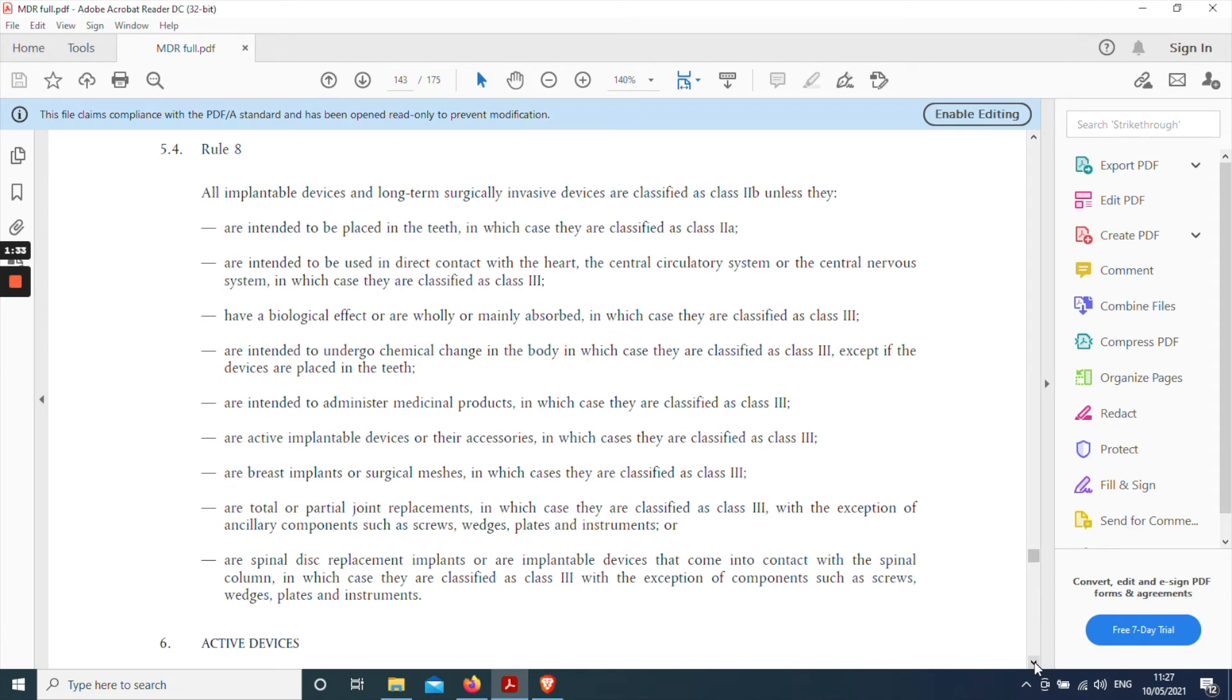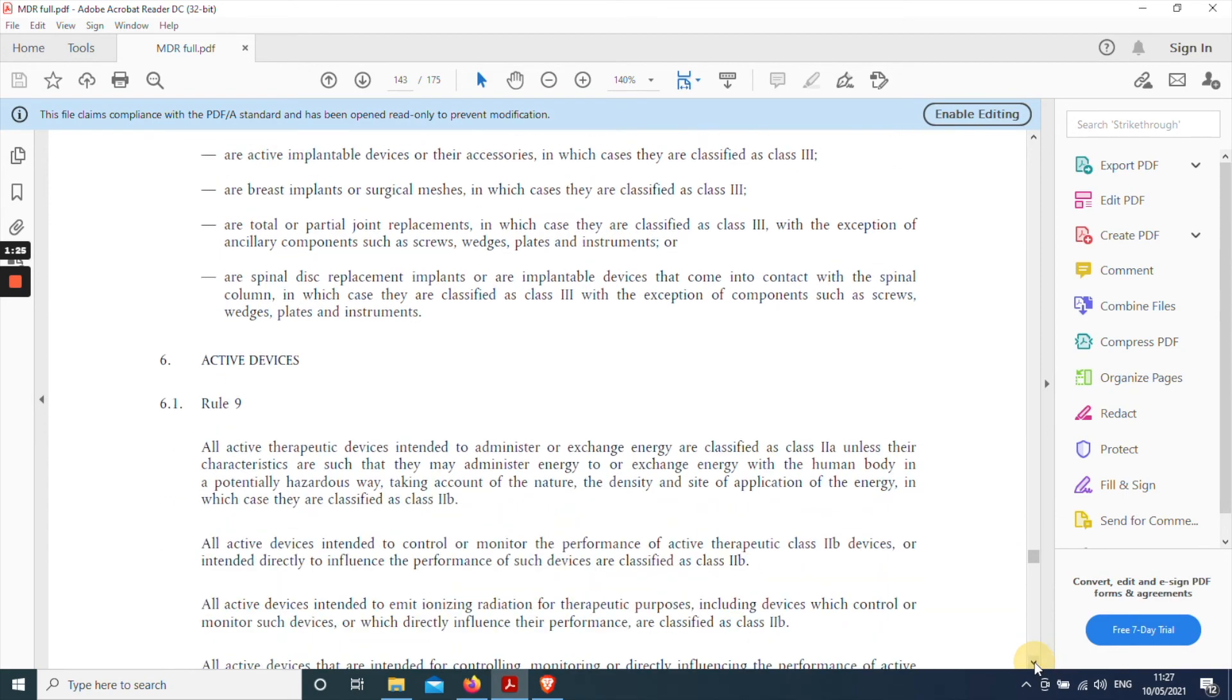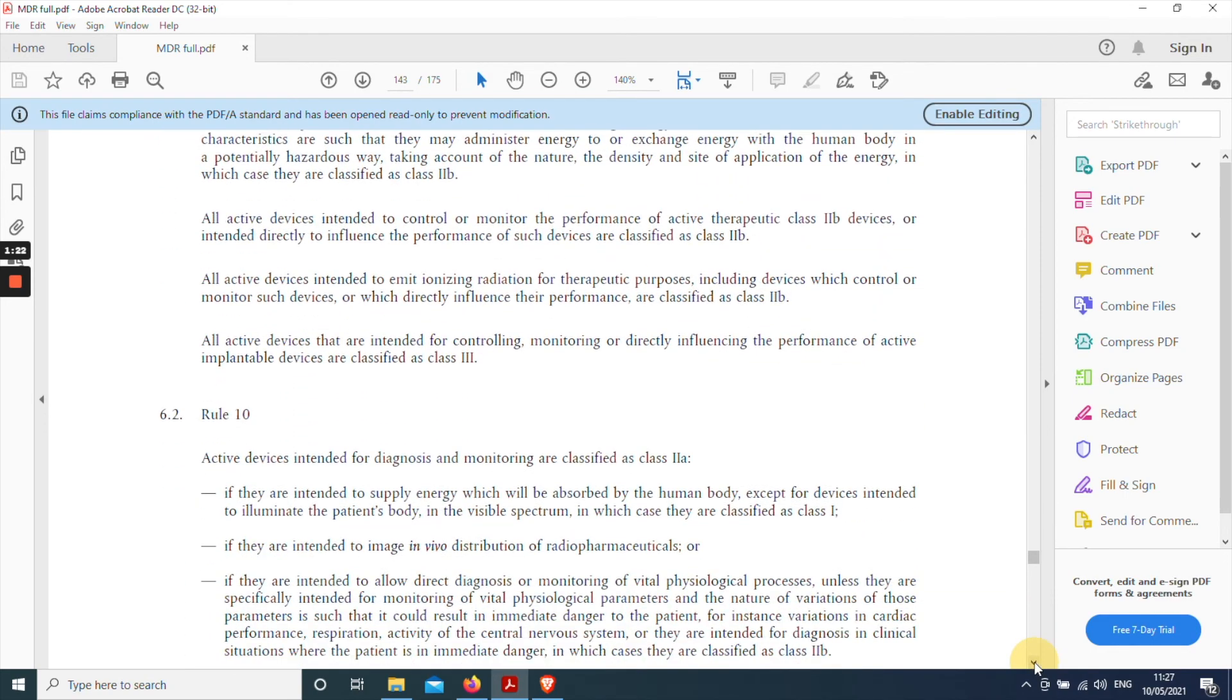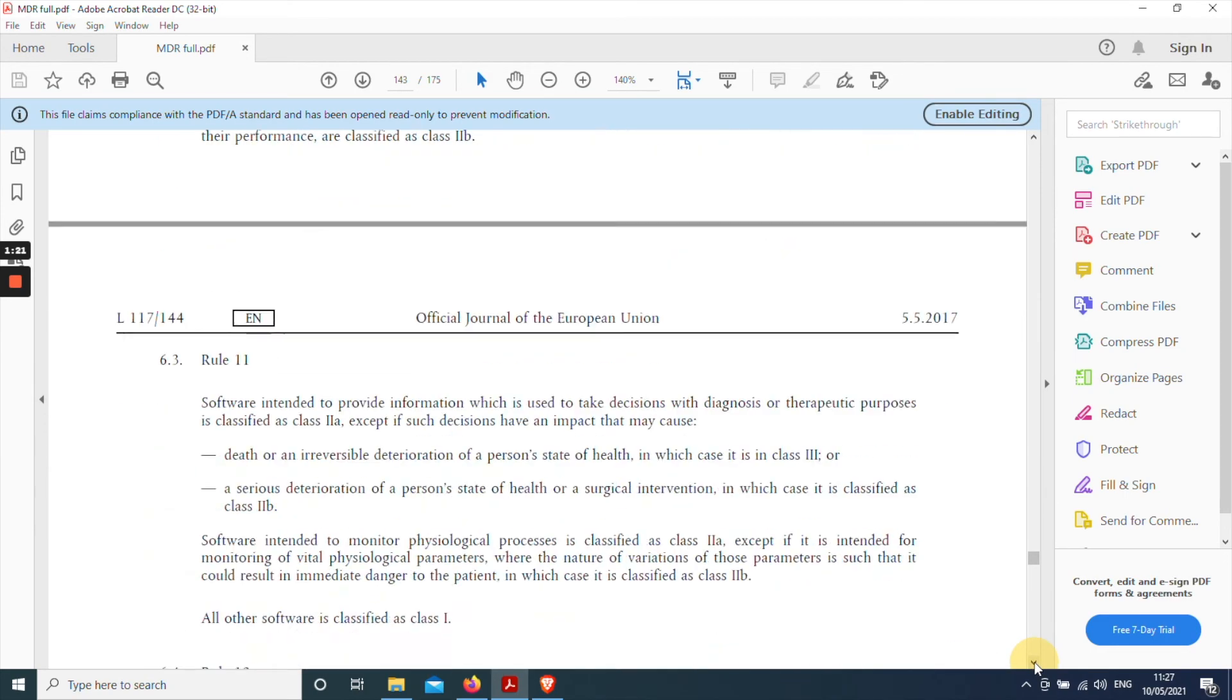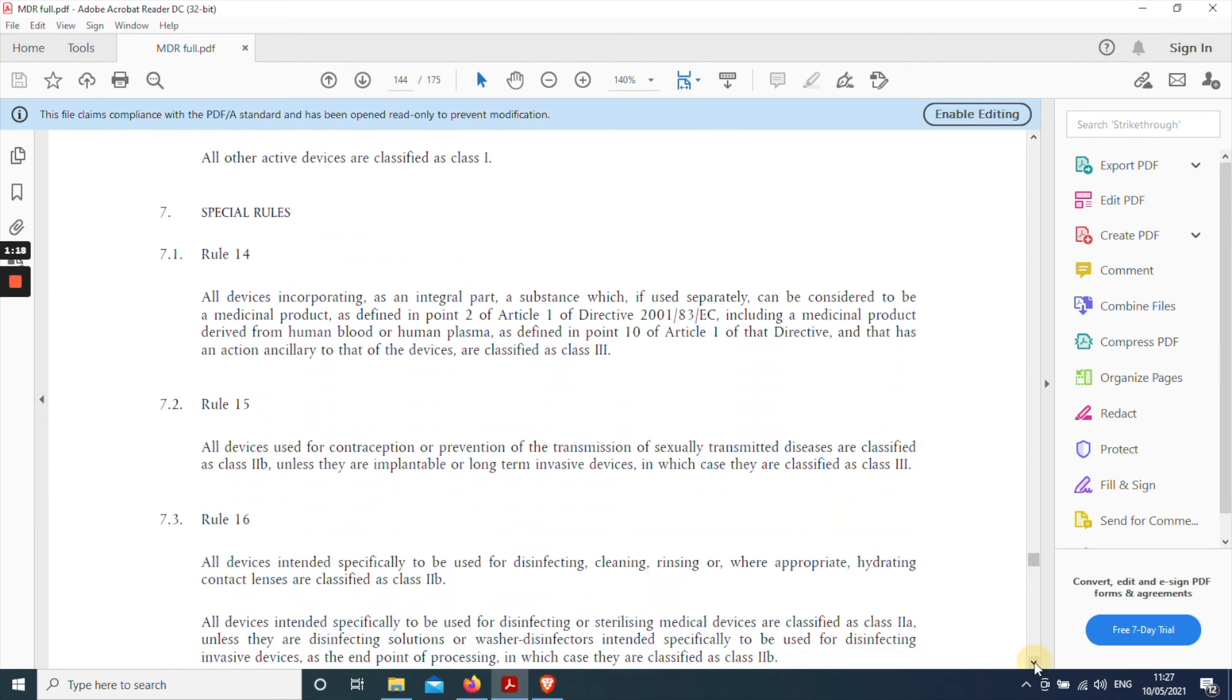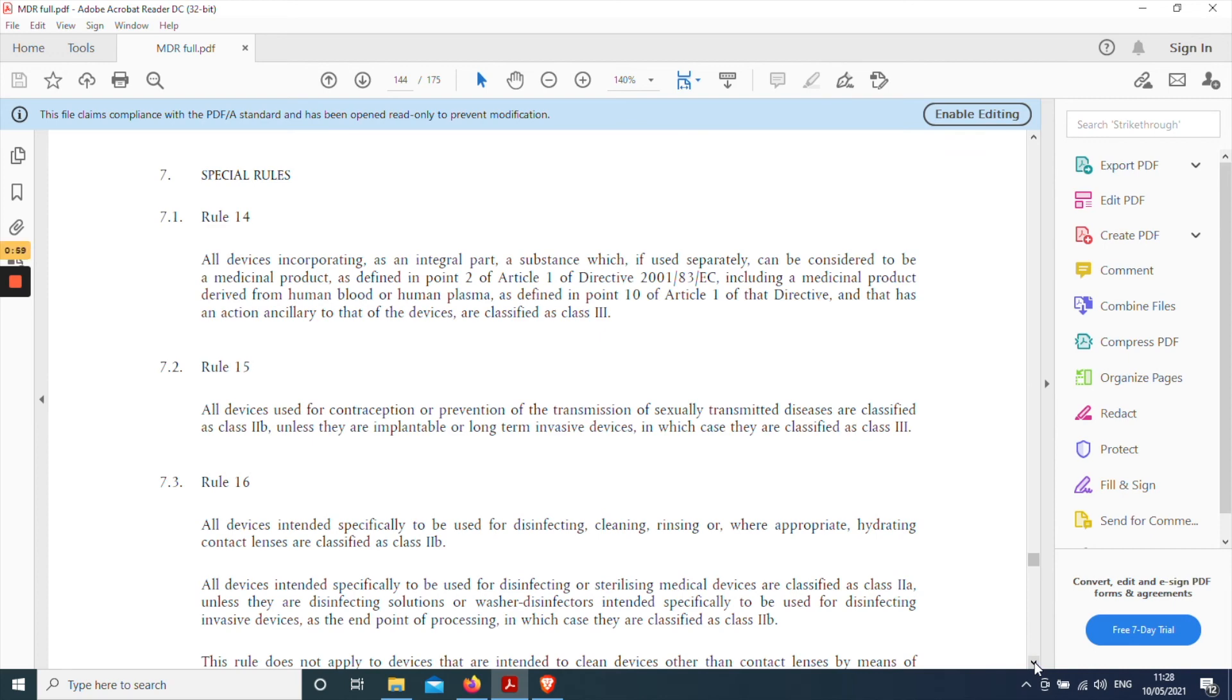So best practice is to, even when you have a fairly confident classification as we do in this case, best practice is to carry on through the remainder of the annex to see if any of the other rules apply. And particularly relevant is the final section beginning with rule 14 which is classified as special rules. Now these are important generally but especially so if you have anything other than a class 3 device because these special rules paper over the cracks that are left by the other classification rules and on several occasions will upgrade the classification of a particular product. So always check these special rules to see if any of them apply.